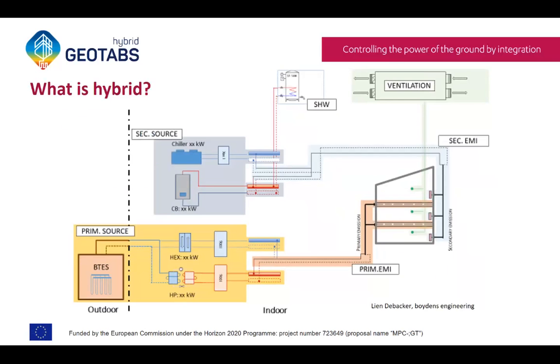It could be replaced by a district heating or cooling system that can act as a secondary supply, combined with some emission system, could be fan coil units, or coils in the air handling room by room, since we have ventilation anyway for indoor air quality. So the secondary system could actually be quite cost efficient, just there to help overcome the challenges of the most performance-based system, the GEOTABS.